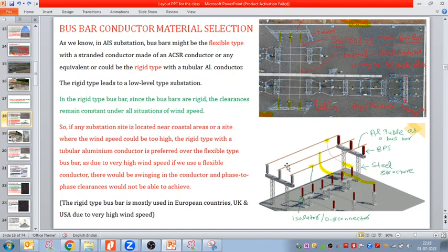If we have the flexible bus bar and the wind speed comes, there would be swinging in the conductor. When the conductor is swinging, suppose your Y phase is swinging, it can come closer to the R phase or the B phase. In that case, the required phase-to-phase clearances would not be maintained. How to avoid the swinging? Anyone could tell me how? Dampers, spacers, yes. Okay, anyway, the swinging will be there in the flexible bus bar.